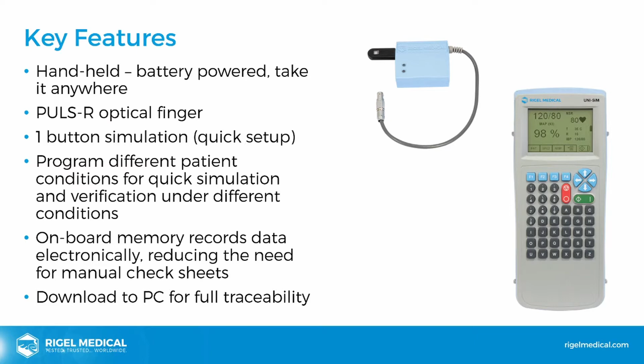So the Rigel Pulsar, this is the simulation accessory for the Uni-Sim. It's got a large number of default curves, manufacturer specific, customised R curve for full flexibility, SpO2 settings from 30 to 100% O2 saturation. We've got signals coming from the monitor which are in a closed loop, red and infrared, and both ways are tested in red and infrared wavelengths. Now with this method, the monitor, extension cable and sensor are tested all at the same time.